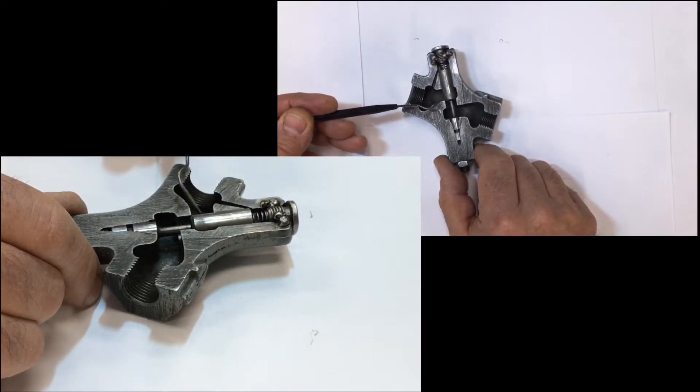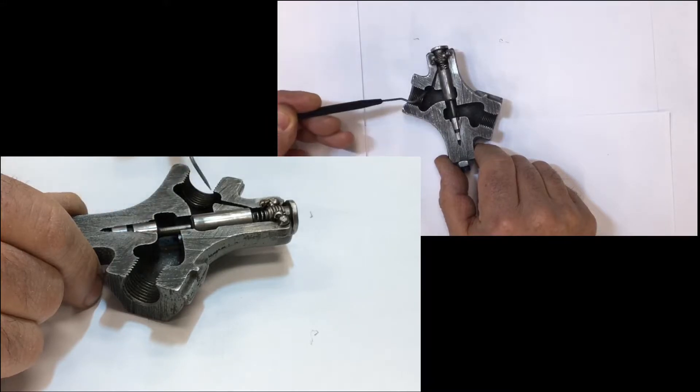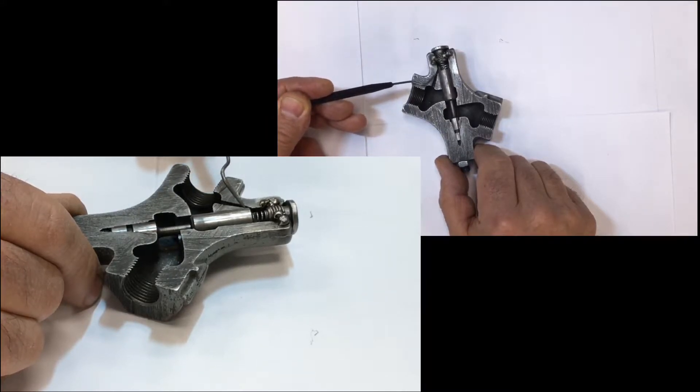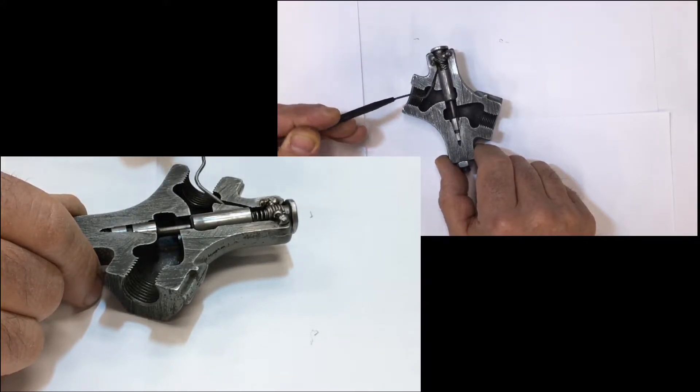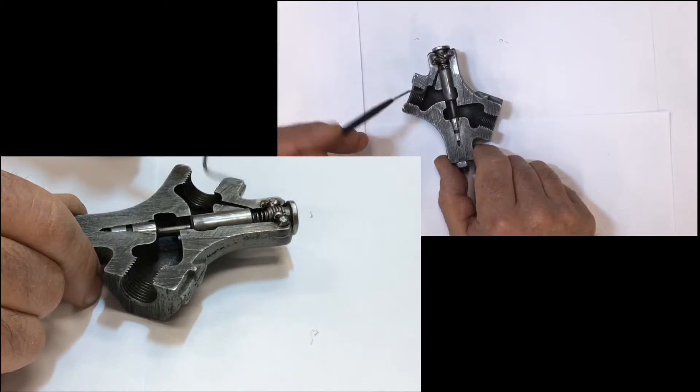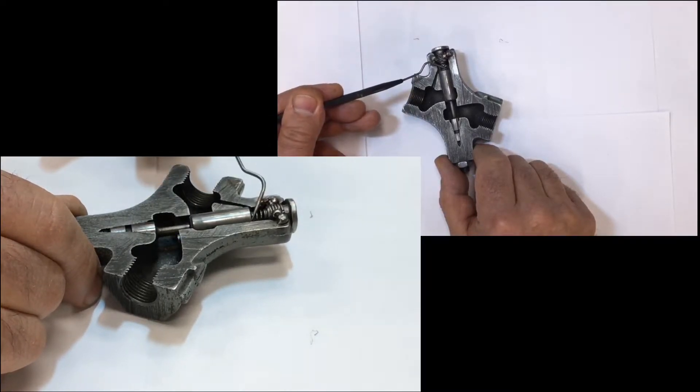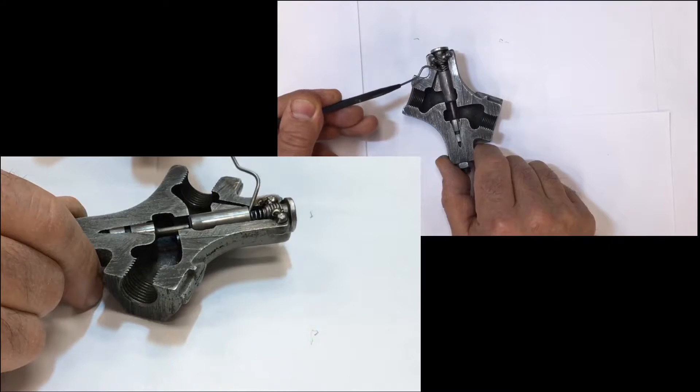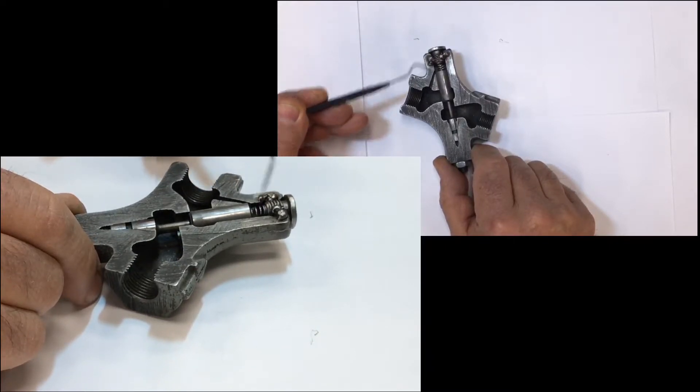Notice that as this oil starts to build up pressure on this side, trying to flow back, it actually goes up this cutaway or this little groove up here and fills the spring cavity. That'll hydraulically lock this check ball and prevent it from opening.